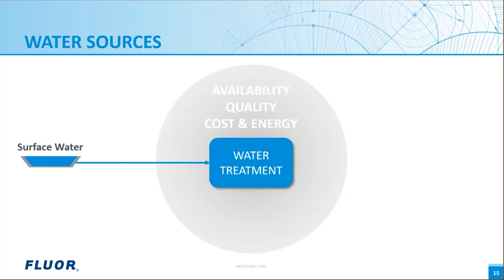Compared to other sources, surface water is usually the most cost-effective option. Availability of surface water varies from location to location, and it should not be assumed to be available in sufficient quantities. Typical contamination includes suspended solids, organic matter, silica, and residual dissolved solids. These waters are not typically difficult to treat. However, variability in composition due to weather and seasonal conditions require robust designs with multiple design scenarios. Surface water is often the lowest cost for treatment.